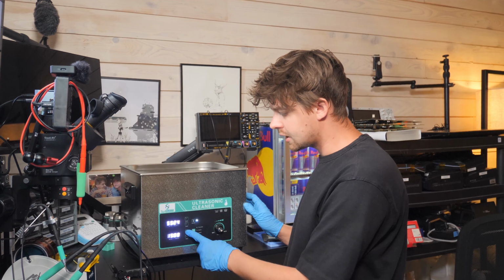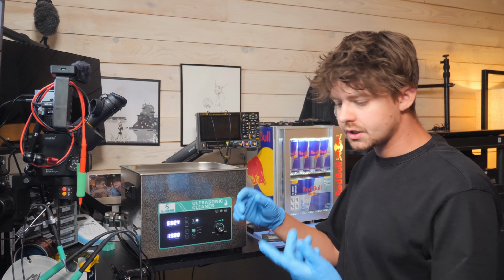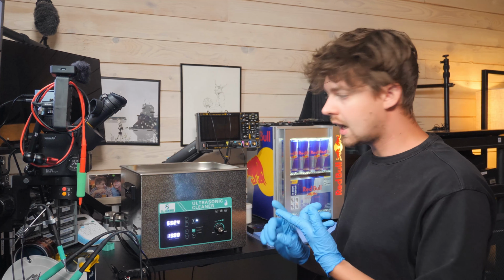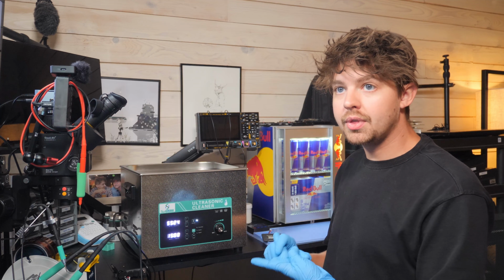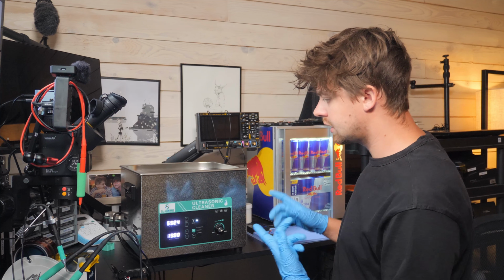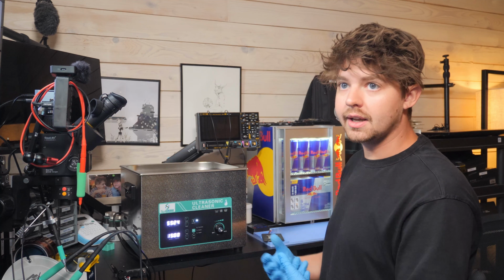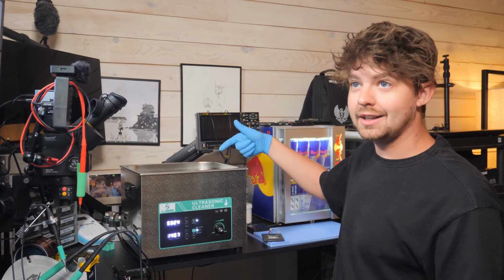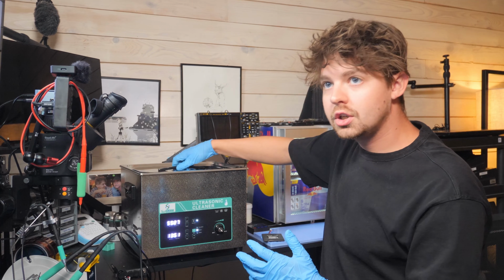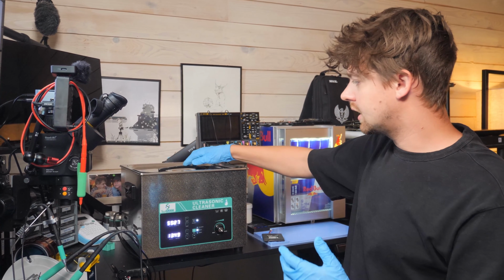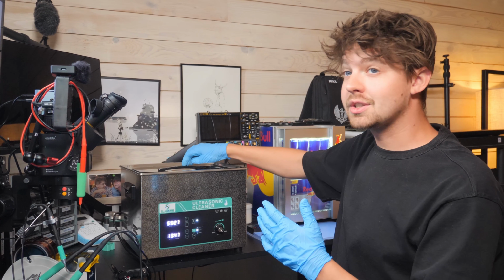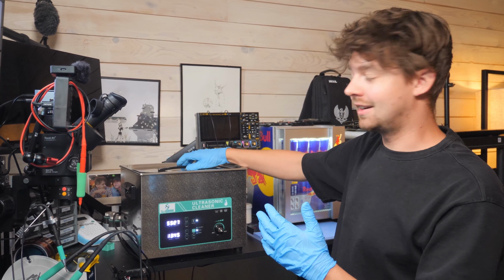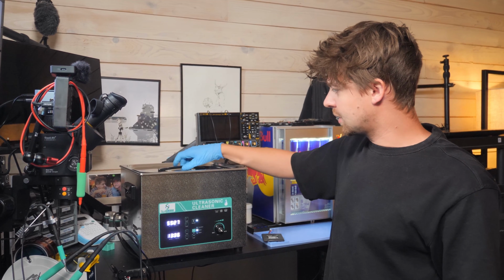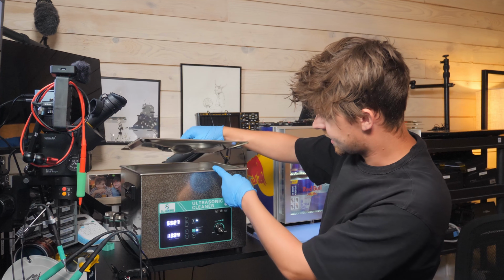One of the things we can do to help this thing get up to temp is actually run the degas mode for 10-15 minutes. This is going to both make sure our liquid is degassed, and it's also going to help the liquid get up to temperature faster because it's going to kind of agitate the liquid. And I can see it's definitely doing its thing. I'm going to put the lid on too, which will help it get up to temp faster. They say it's quieter with the lid, but it's not quieter with the lid. Oh my god, it's actually much louder with the lid because this part dips into the liquid.